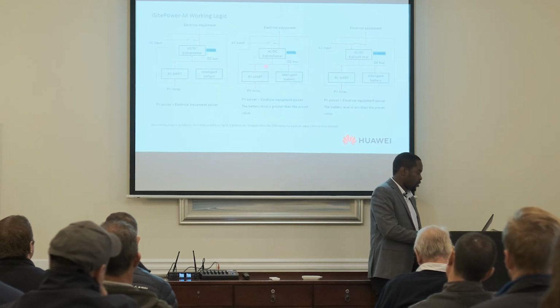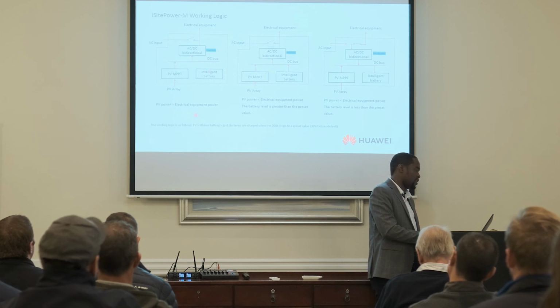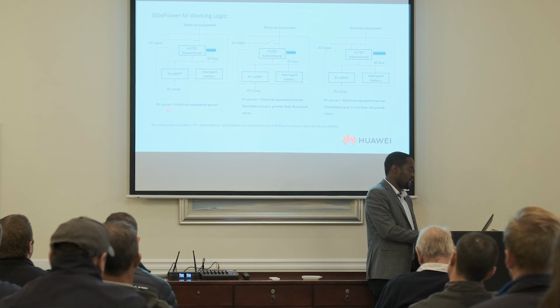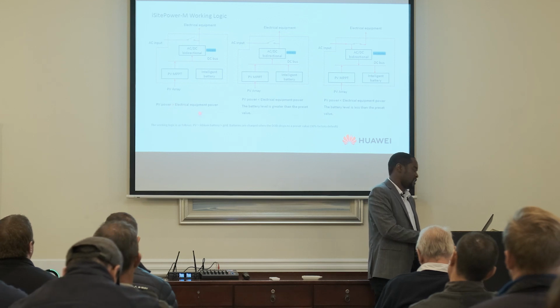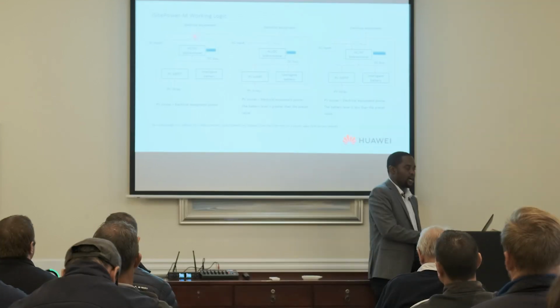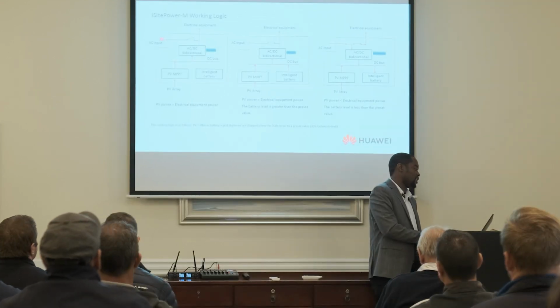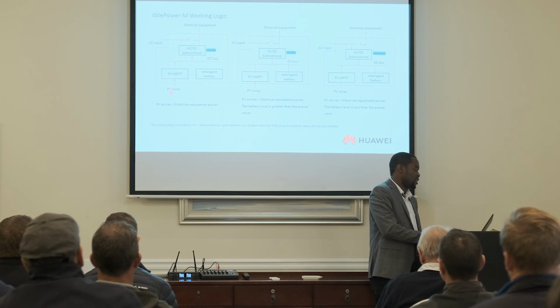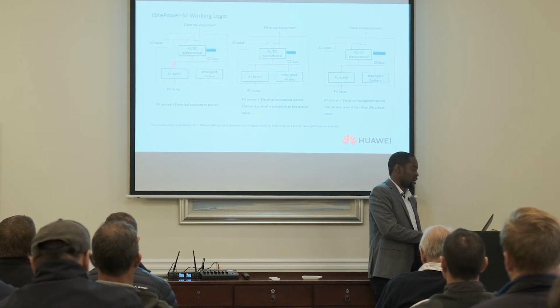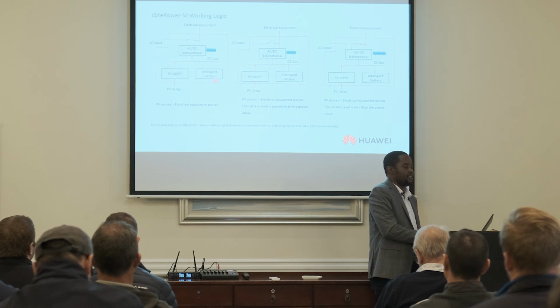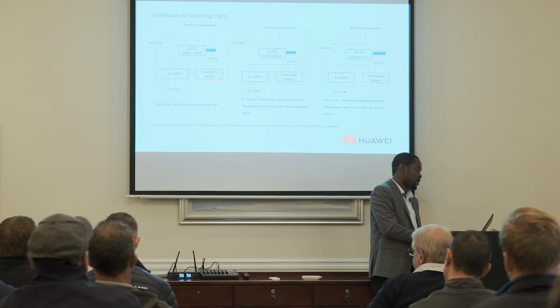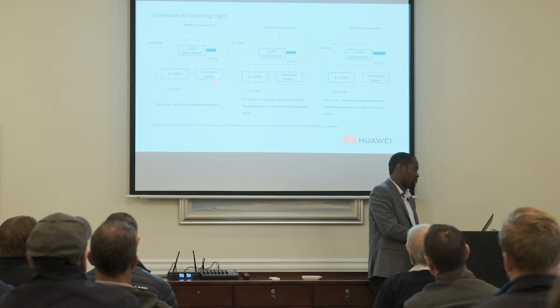Then the different work logics, the modes. For instance, this one is when your PV power, that is your production, is greater than your demand. You don't need AC, which means your bypass or AC internal relay will be open. You are not taking anything from grid. You're actually using what you are producing from your PV plant. You are using it to supply the loads here and also to charge the batteries if you've got extra power and if your batteries are not full, right?